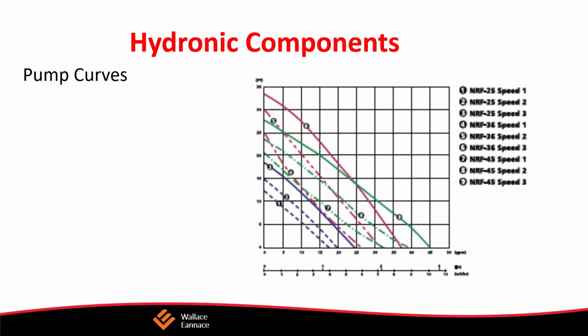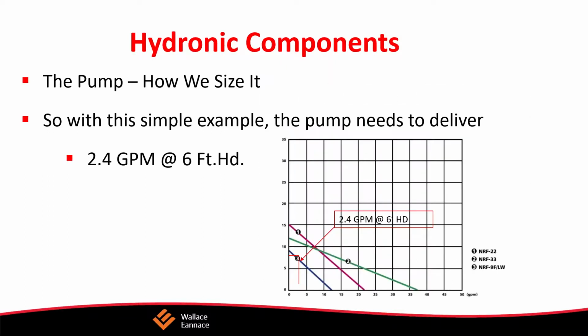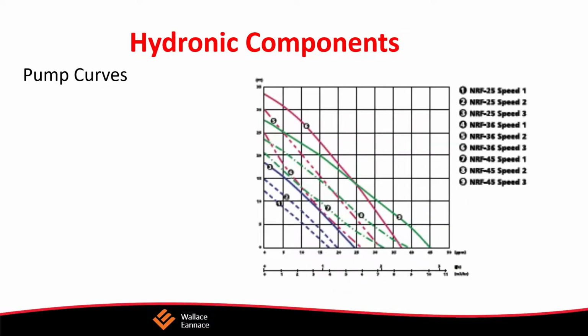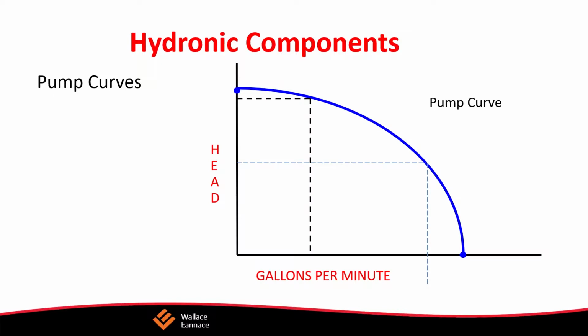How much resistance does a pump have to overcome to get the water where it needs to go? So system flow is like a Ferris wheel. The weight of the water going up is equal to the weight of the water going down. And the pump needs only to overcome the friction of the system. As you can see by just looking at this image, the weight of this water pushing this way is equal to the weight of this water going that way. And it's really only at this center point that it needs to overcome the system.